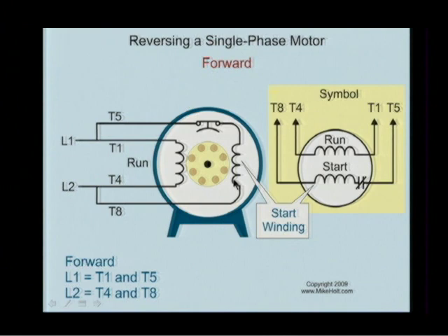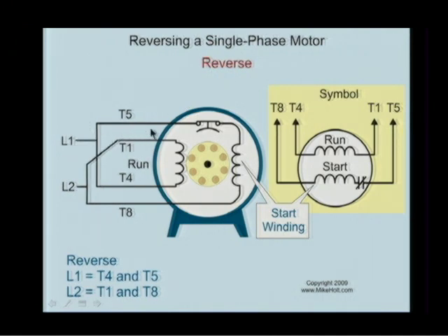Right. Yes. Okay. Now, if this is line 1 and this is line 2, they're still in parallel, just different polarity. I've got to follow this. This is line 1 that comes over here, but this is line 2. But this is line 1. Oh, no, this is line 2. Yeah, we swapped the run leads in this drawing, which will work equally as well. You just need to swap the relative polarity of the start with the run.